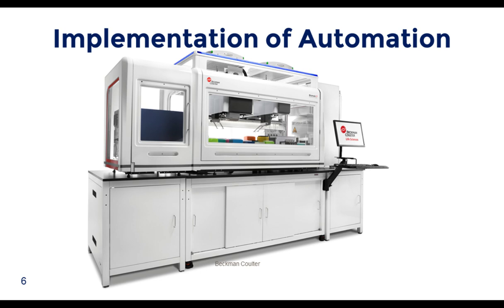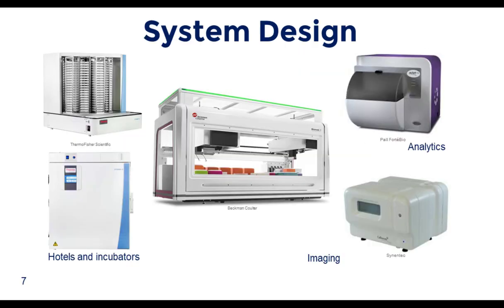One way to address decreasing resources while handling increased clone throughput is automation. Process steps like incubation, plate imaging, and clone evaluation can be integrated with liquid handling scale-up steps, allowing more clones to be processed with fewer resources. The automation system includes a liquid handler at its core, integrated with ambient storage hotels, incubators, imaging devices for monoclonality or growth monitoring, and analytics devices. All or part of the system can be enclosed in a laminar flow enclosure to maintain sterility.